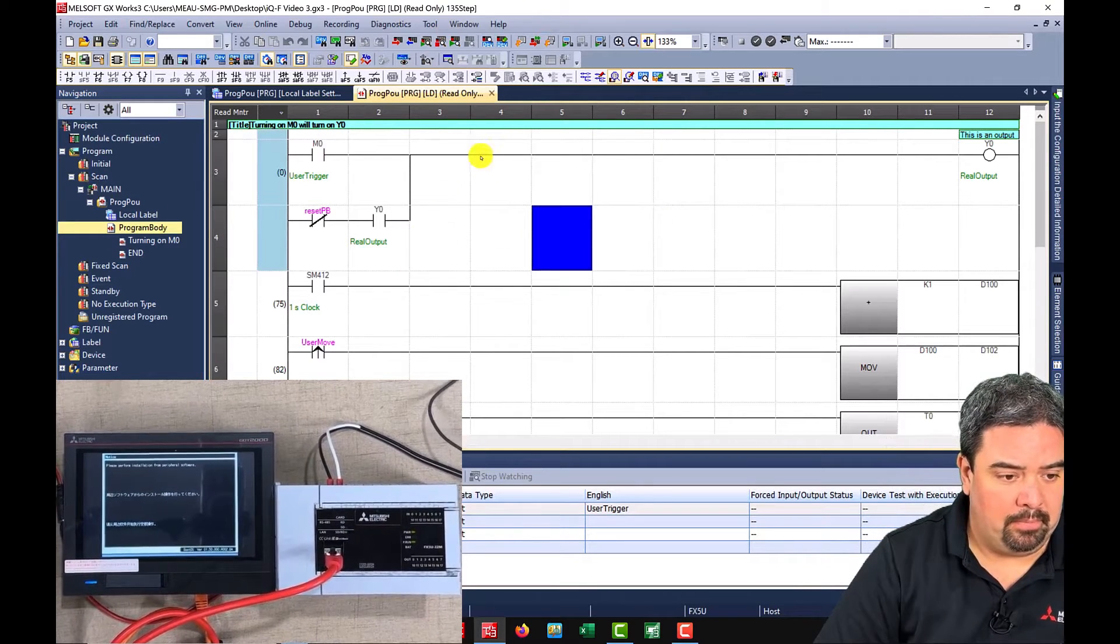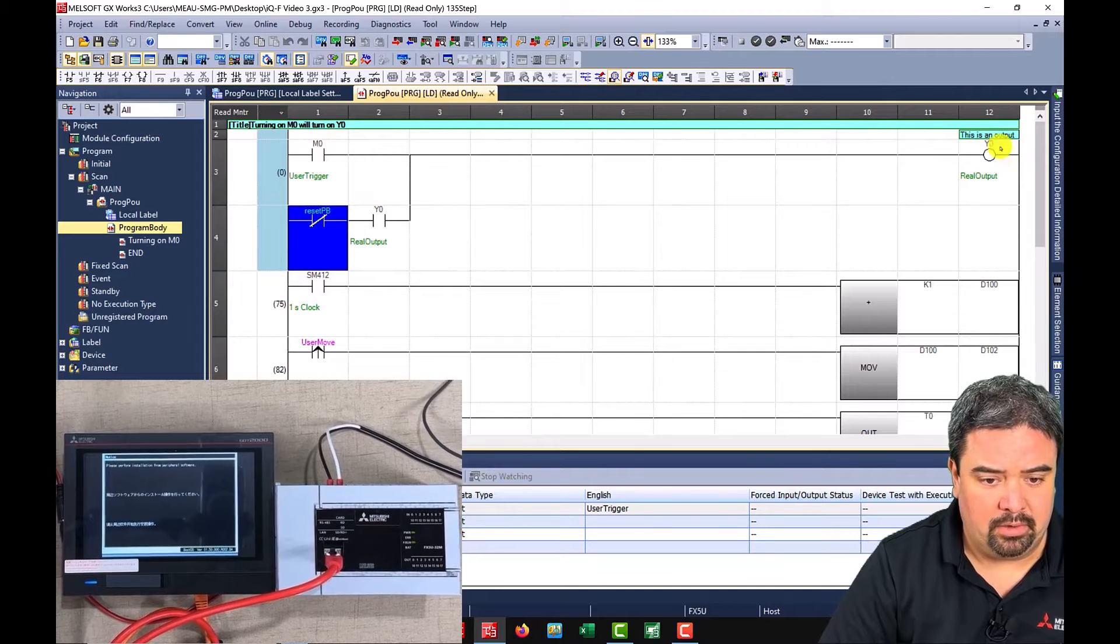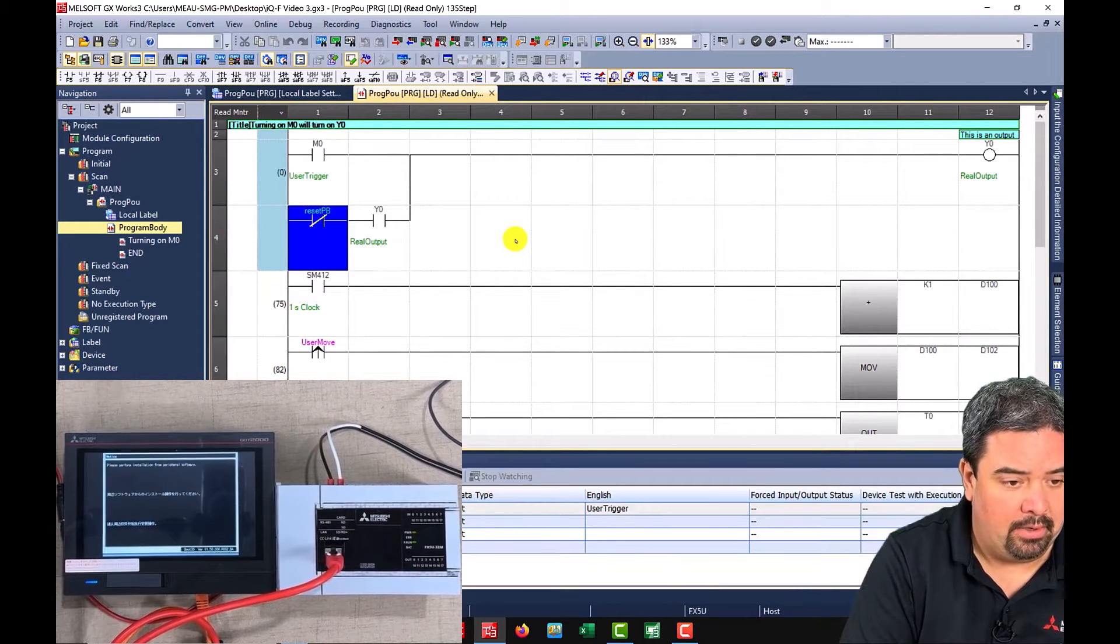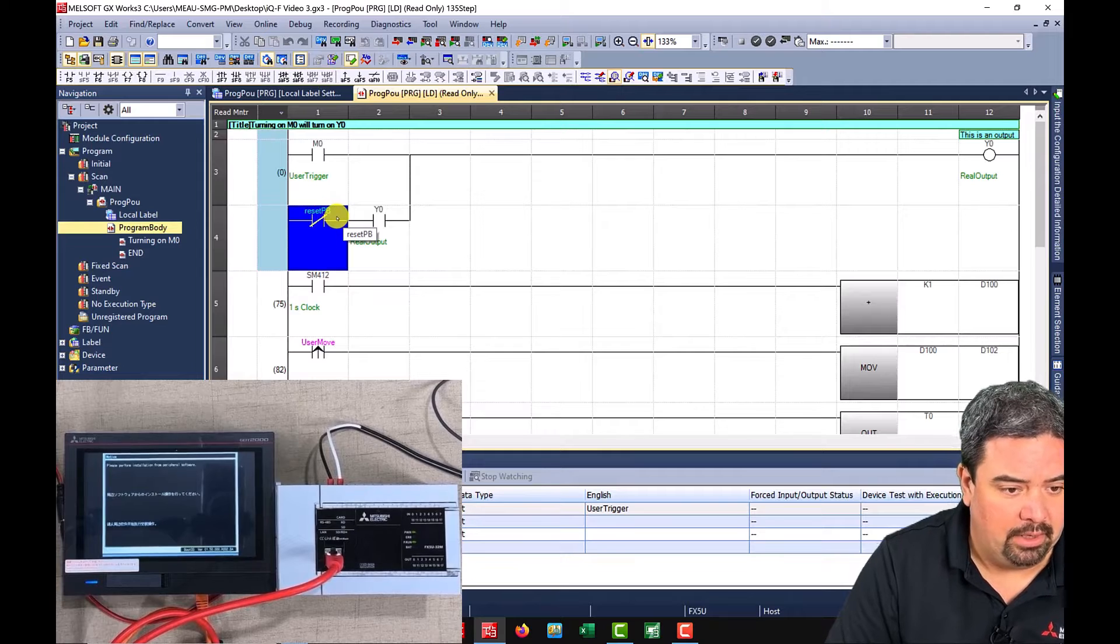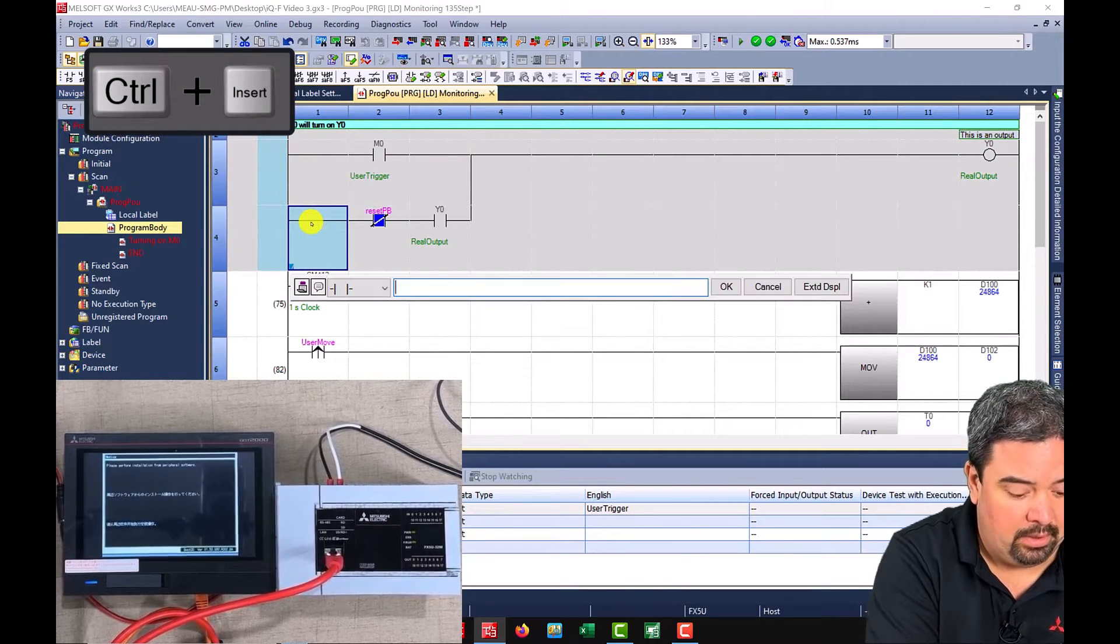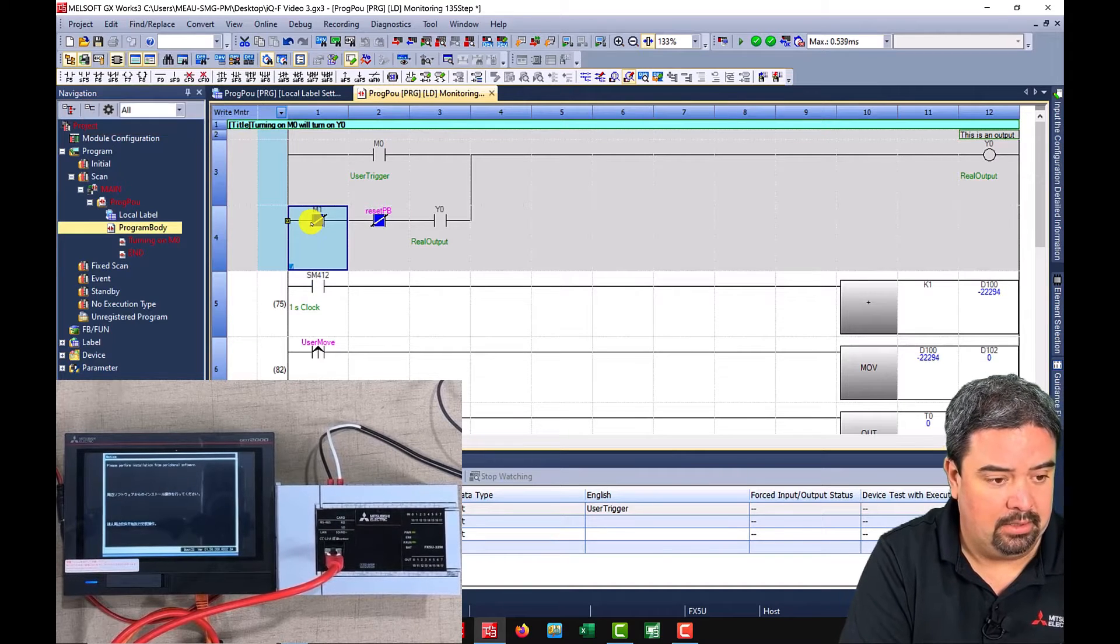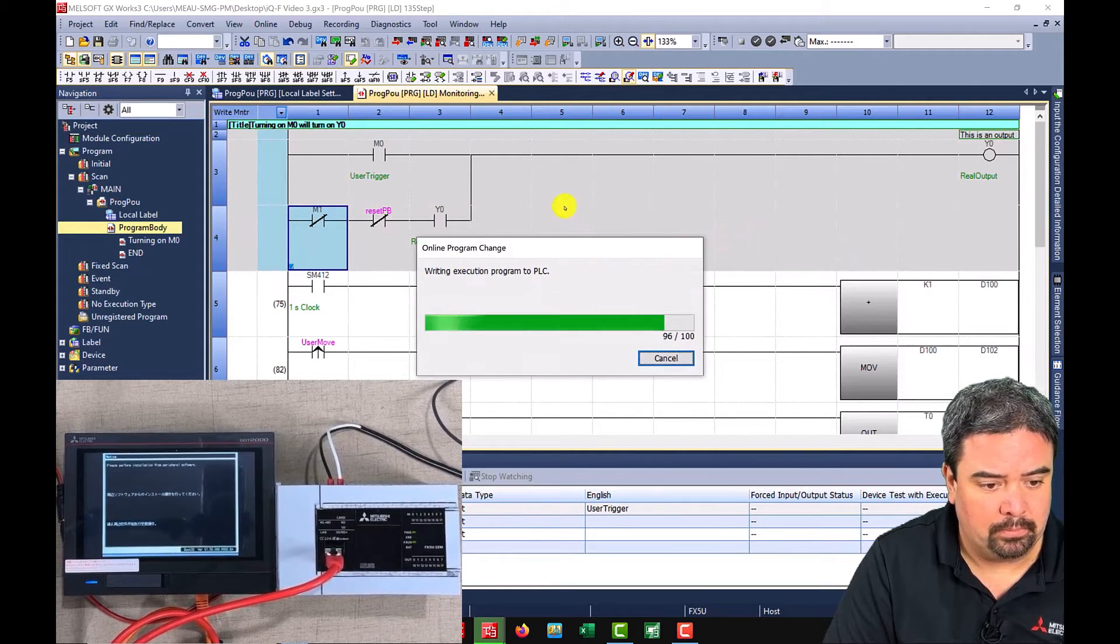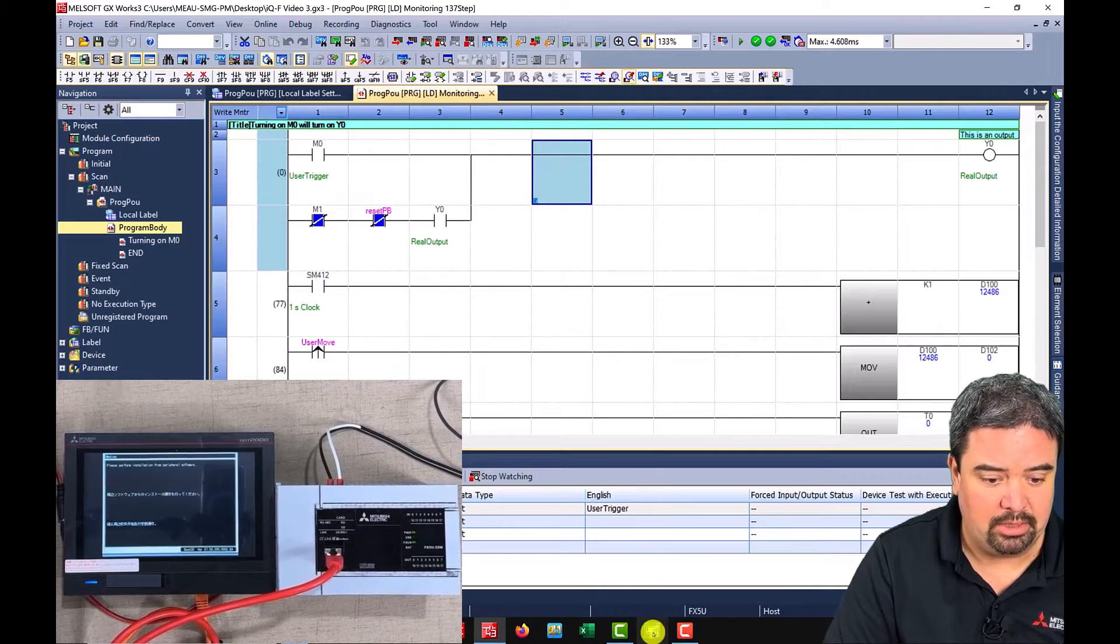We'll open up our project and maybe one of the first things we'll do is allow this M0 to be displayed on the HMI and we will turn on Y0. So we'll also display that and then we'll give a reset. This video is not going to go over labels so I'm just going to add another element to do the reset that the HMI can see quickly. If I go into write mode I can control insert and I'm going to put a normally closed, so F6 M1, and that will become our reset. And now we can monitor this and we can see that Y0 is not on and M0 is not on so let's add that to our GOT project.